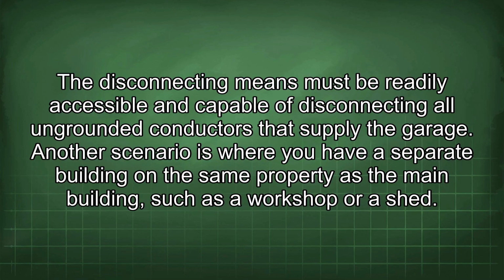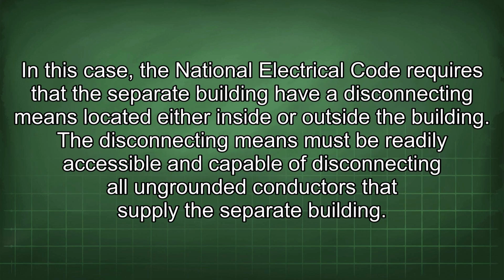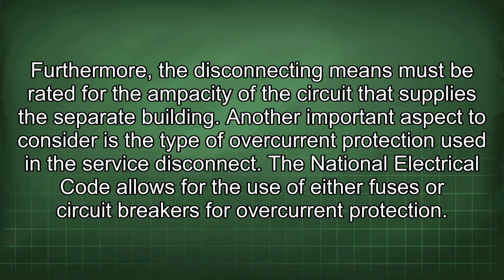Another scenario is where you have a separate building on the same property as the main building, such as a workshop or a shed. In this case, the National Electrical Code requires that the separate building have a disconnecting means located either inside or outside the building. The disconnecting means must be readily accessible and capable of disconnecting all ungrounded conductors that supply the separate building. Furthermore, the disconnecting means must be rated for the ampacity of the circuit that supplies the separate building.